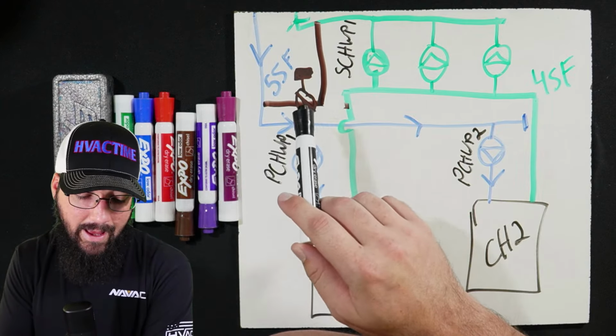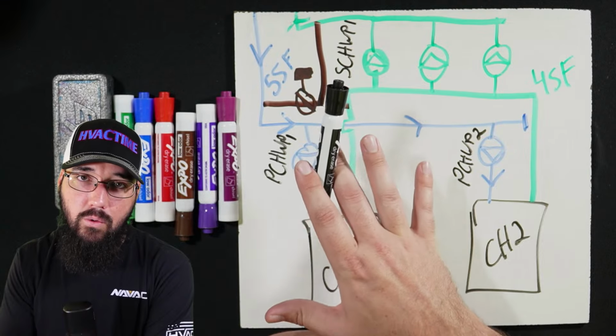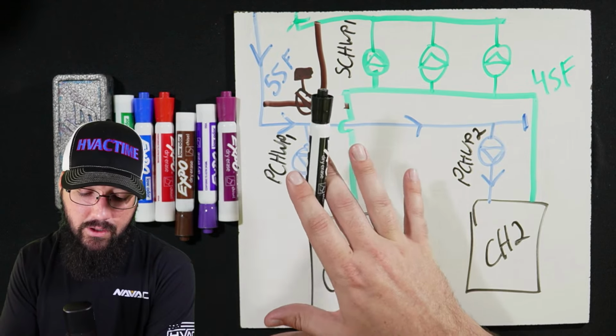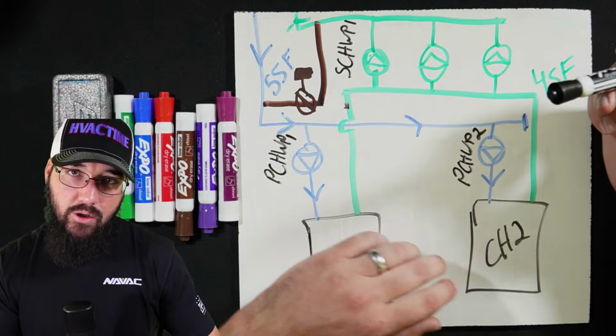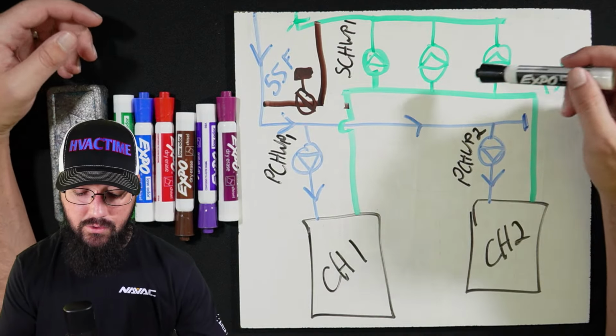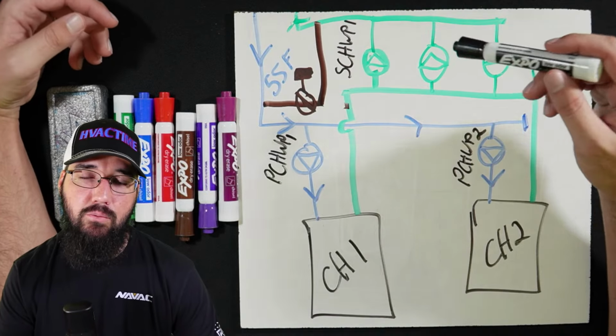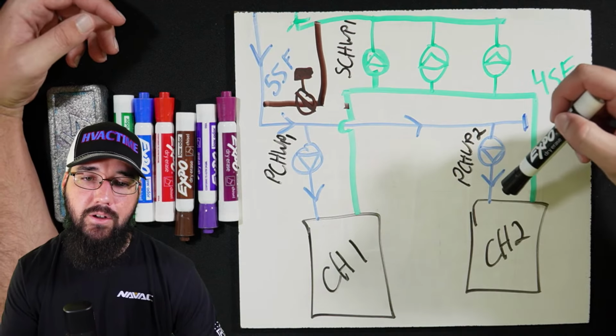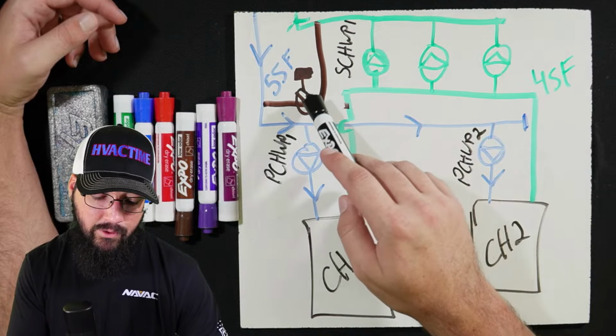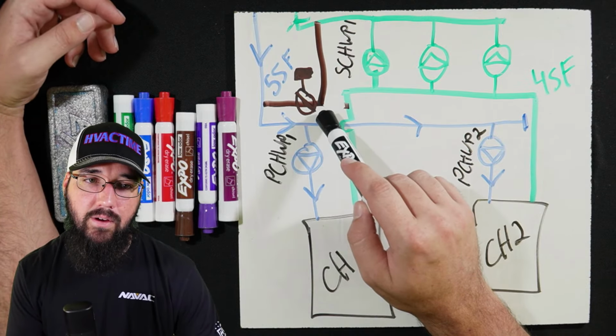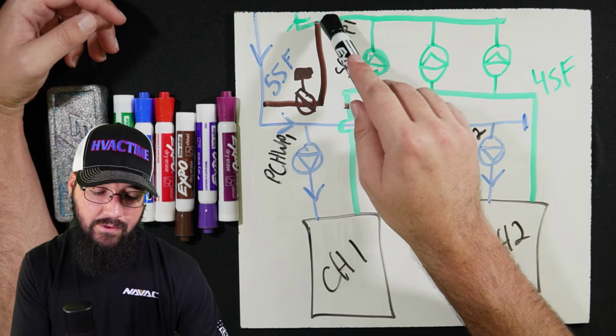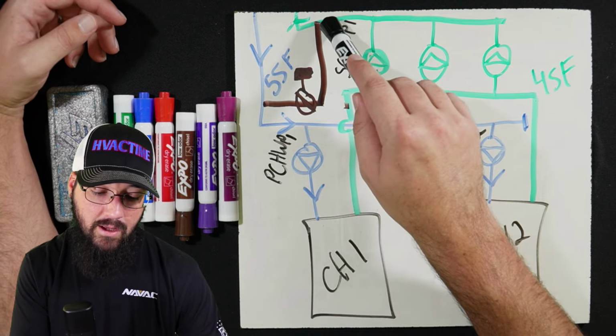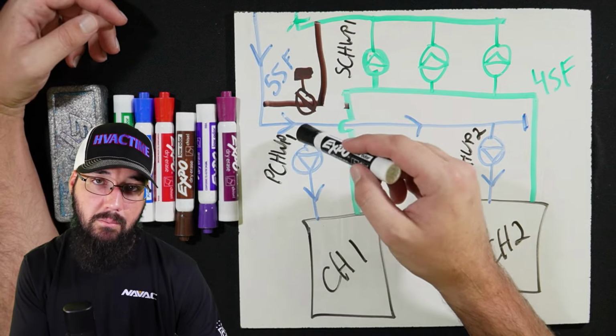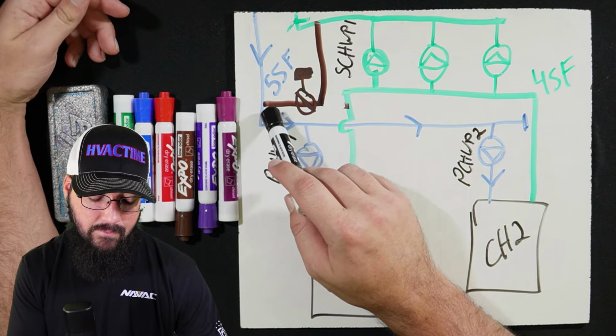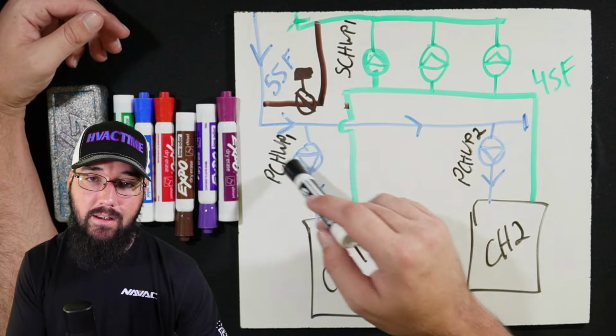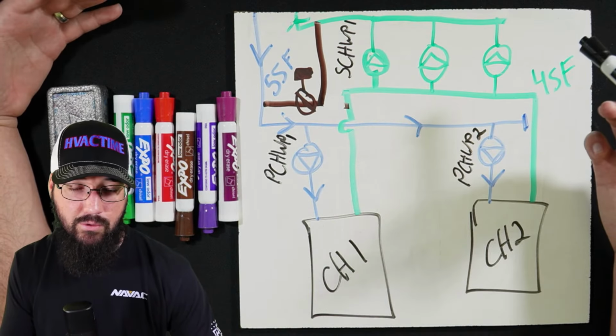And as we begin to get lower in load, at some point we hit a breakover point where our primary loop needs to move less water through it than what our chiller needs as a minimum. So at some point we start actuating this bypass valve so that we are bypassing water from the supply leaving the plant into the return coming back to the plant, so that we can maintain a set GPM. It's not even about temperature control at that point.